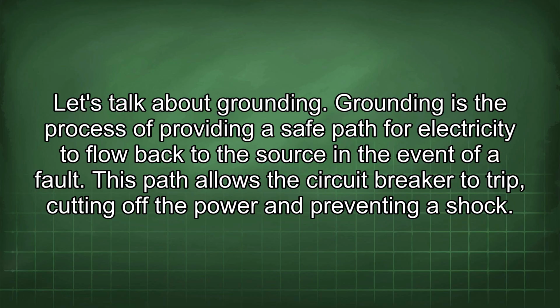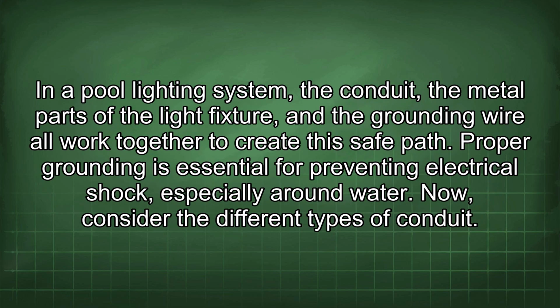Let's talk about grounding. Grounding is the process of providing a safe path for electricity to flow back to the source in the event of a fault. This path allows the circuit breaker to trip, cutting off the power and preventing a shock. In a pool lighting system, the conduit, the metal parts of the light fixture, and the grounding wire all work together to create the safe path. Proper grounding is essential for preventing electrical shock, especially around water.